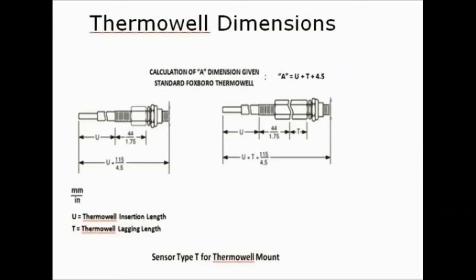The question that always comes up is how much length do I add to the sensor to go through the other connecting parts. Do not add any additional length. All other lengths are fixed and the factory accounts for them when ordering the sensor.